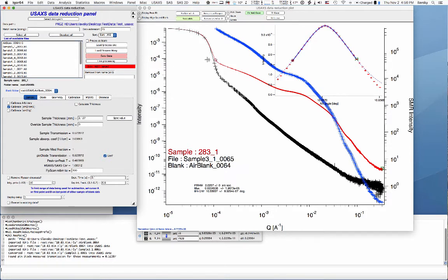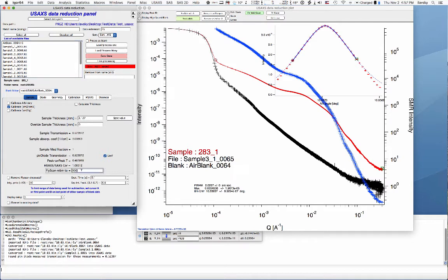The raw data curve has 8,000 points — dense at high angles. Subtracting blank from sample gives 8,000 difference points, but fitting 8,000 points, especially at high angle where it's noisy, is computationally demanding. So we re-bin the data on a log scale to fewer points. 300 points is typically fine; on slower machines people use 100. You can see at 100 the data are sparse and a feature here is nearly wiped out. If you have Bessel function oscillations or diffraction peaks you might need more points. 1,000 points seems overkill for this data.